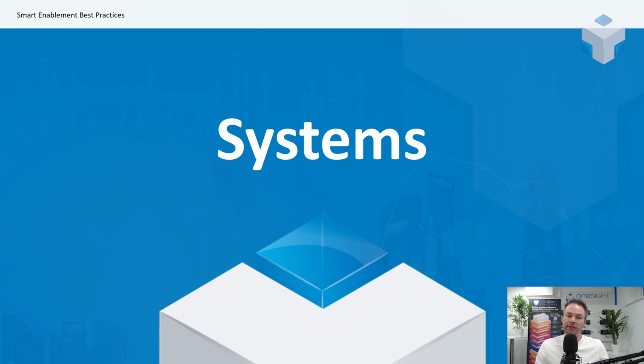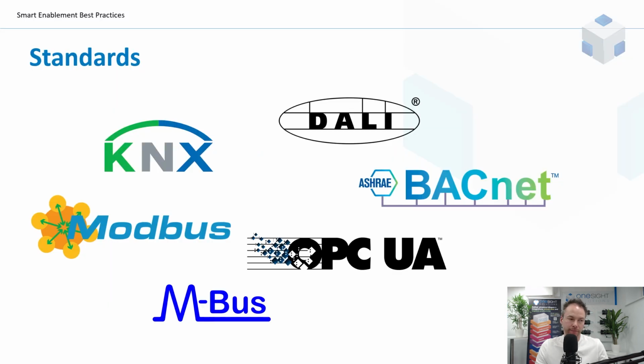As touched on, there are loads of different systems that we can integrate with and smart enable. Thankfully, more often than not nowadays, these systems will be using one of the widely established industry standard protocols that are on offer. Some standards are shown here on screen, and some of them, such as BACnet, KNX and DALI, all have rigorous certification programs. Certification of devices offers a guarantee to the end user that the devices implement the protocols correctly and will function as expected. The three standards I mentioned list any certified devices on their websites.